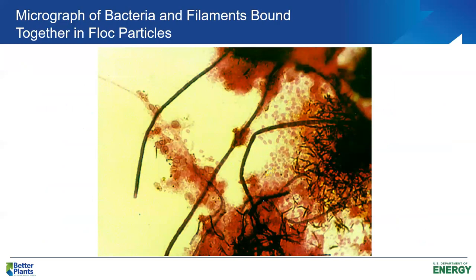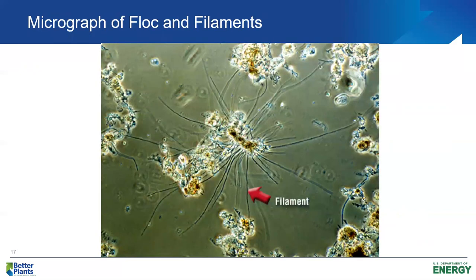Looking again at the micrograph of bacteria, we see clumps of bacteria and also the filamentous organisms that provide floc structure. It's very important to recognize the type of organisms present: small amounts of filaments strengthen the structure, while large amounts can adversely affect process performance. A general rule is if we have more than about 10 to 20 filaments per floc, we're beginning to have too many filaments and may see settlability issues in our final clarifier.